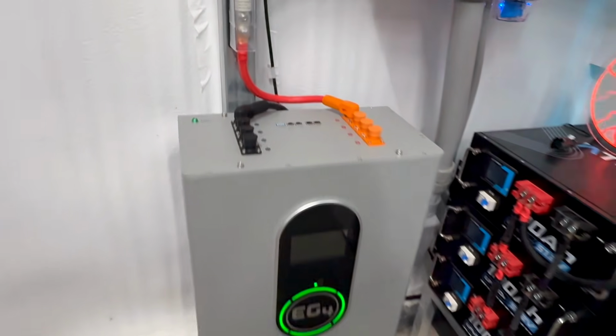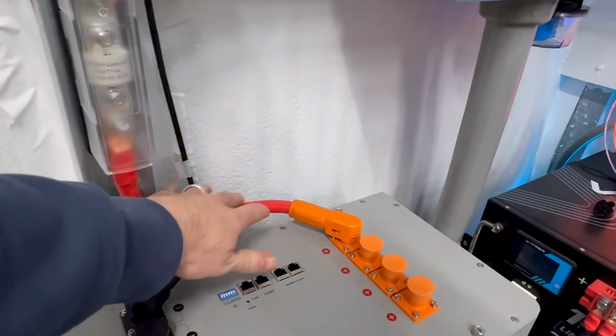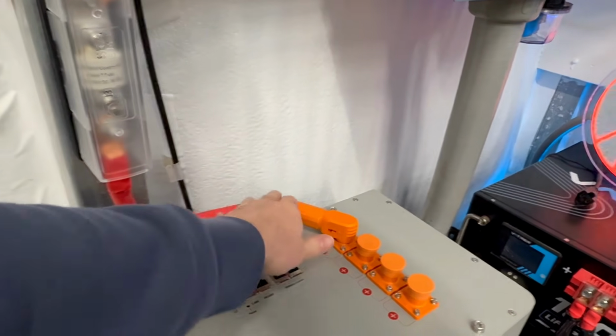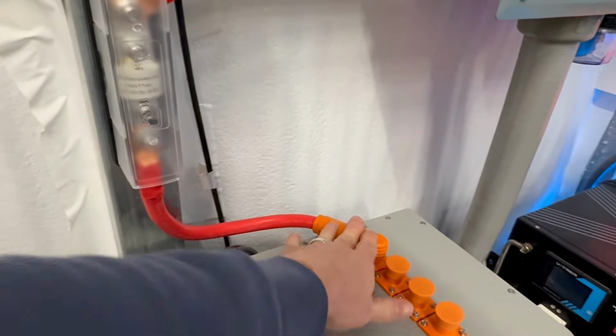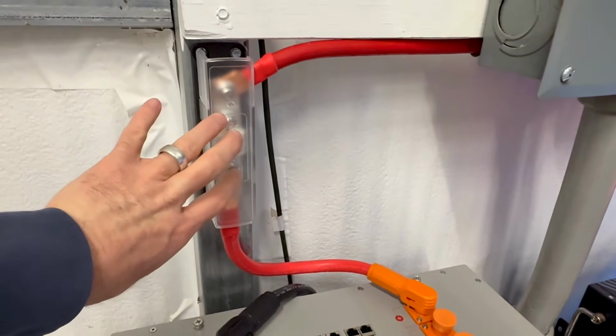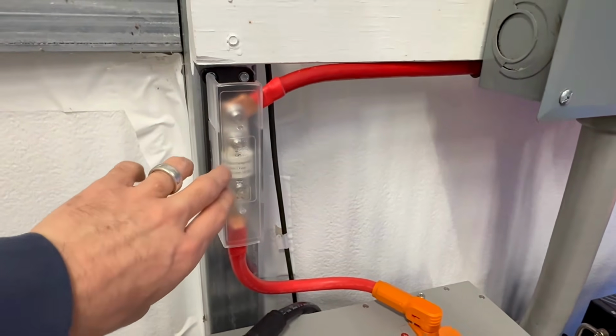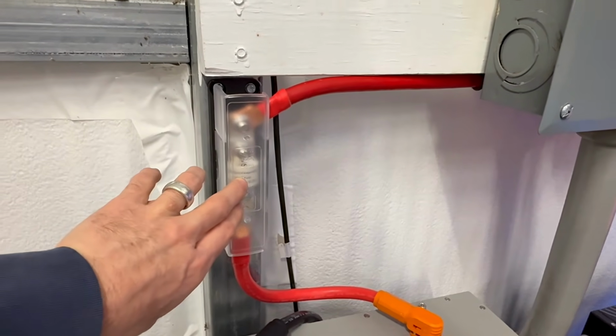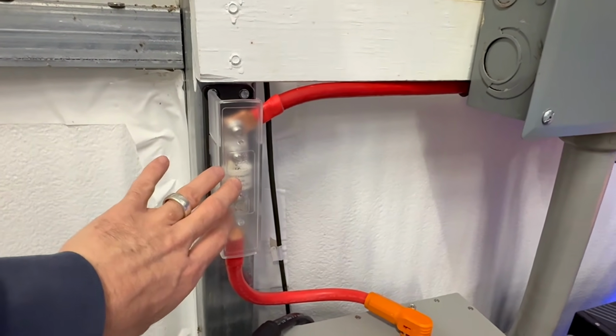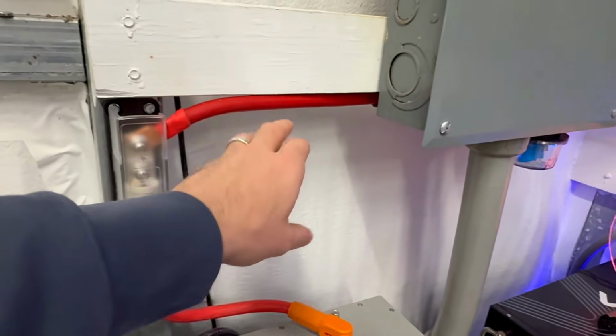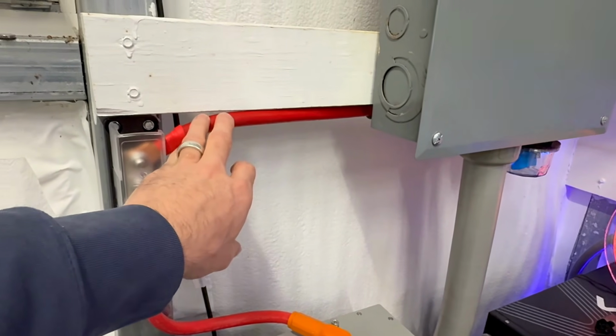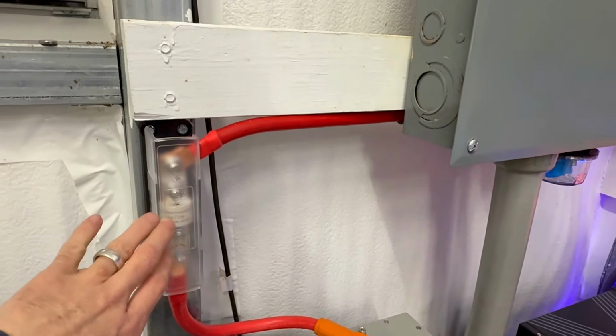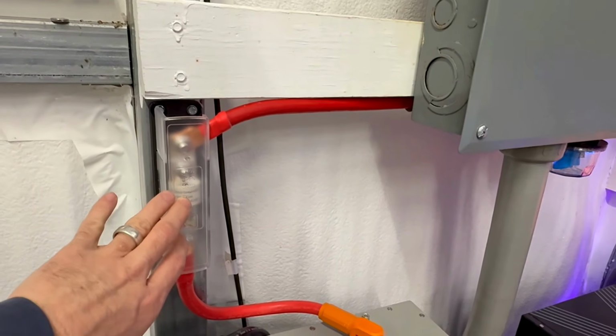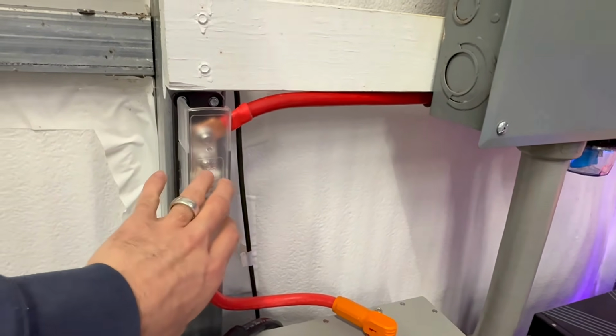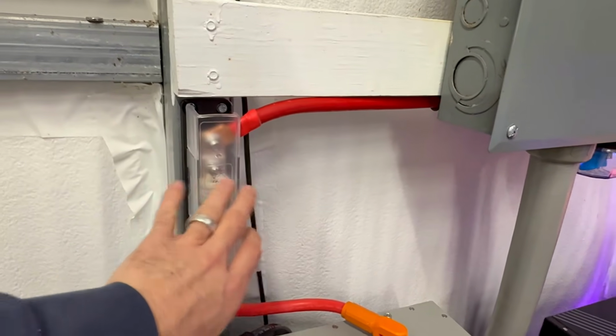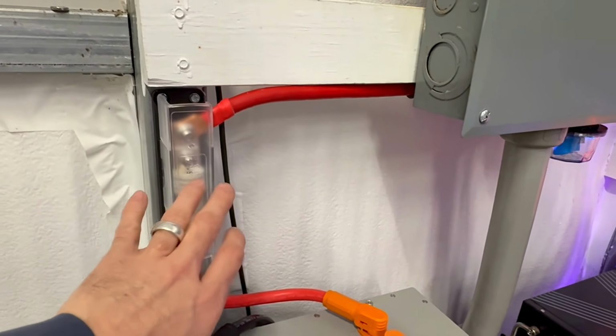Looking at the battery, I'm using the standard 2-aught cable that came with it. It has the Amphenol connector on one end, connecting to my Blue Sea fuse holder. I'm using South Bend UL listed fuses, I believe this is 225 amps. With this being welding wire rated for 90C, the fuse is sized appropriately for it.